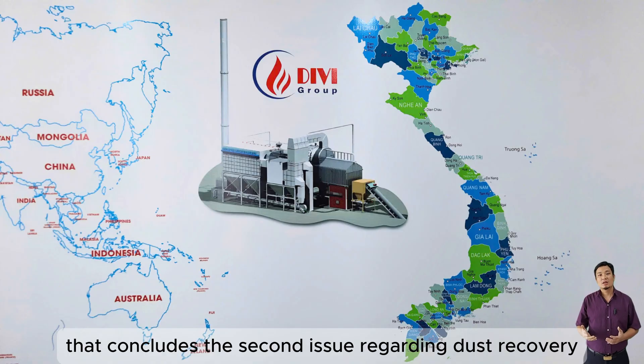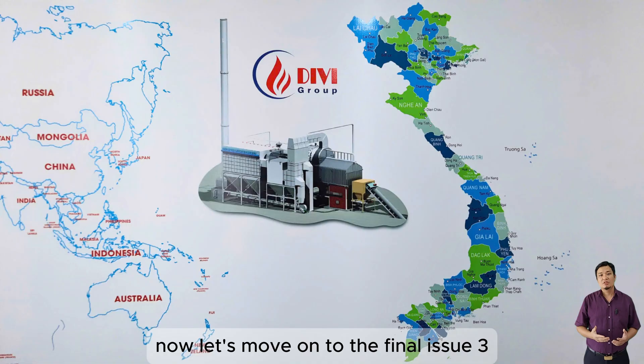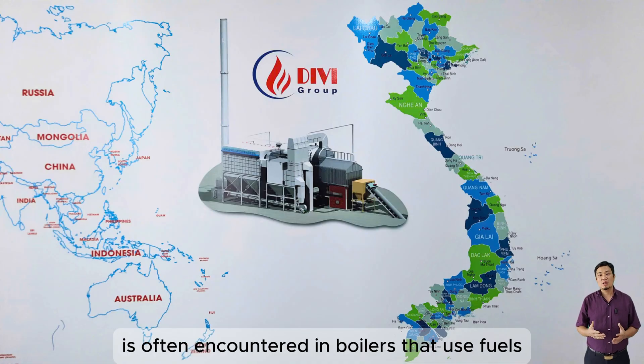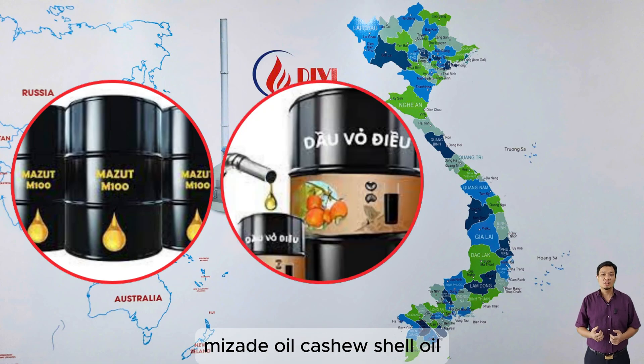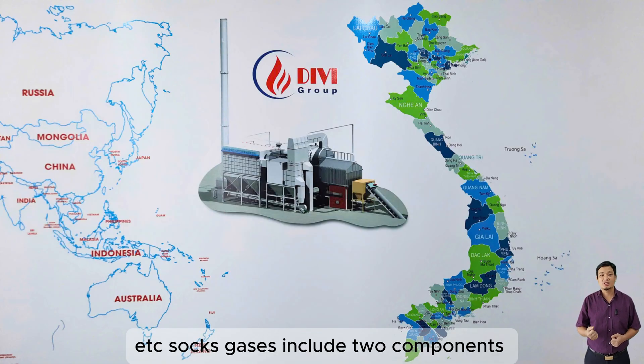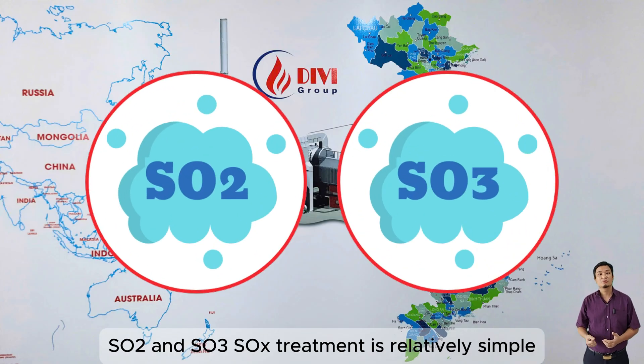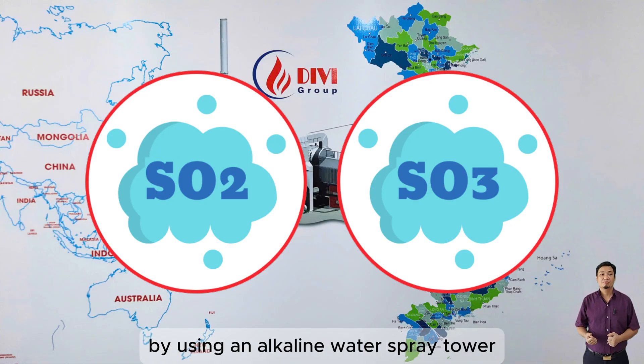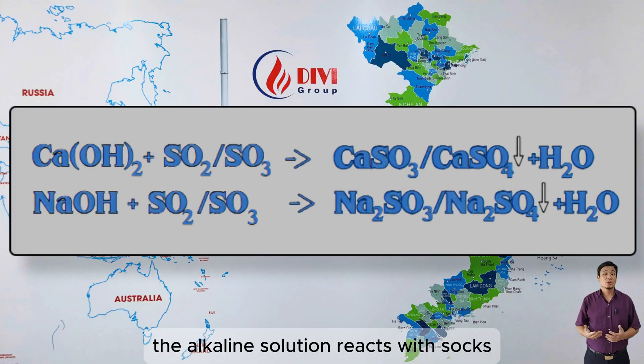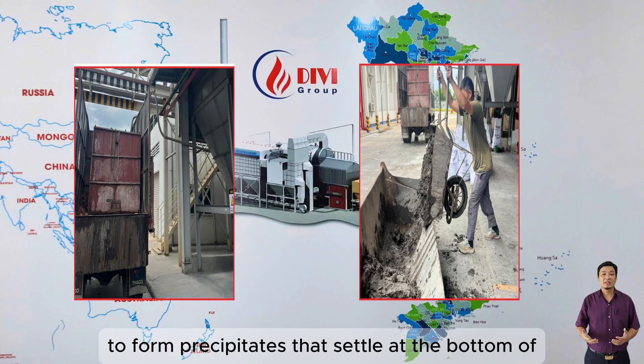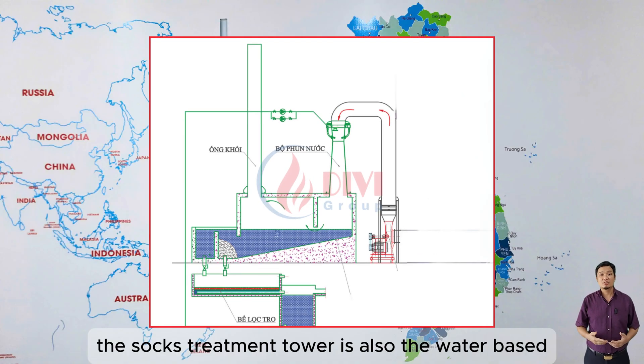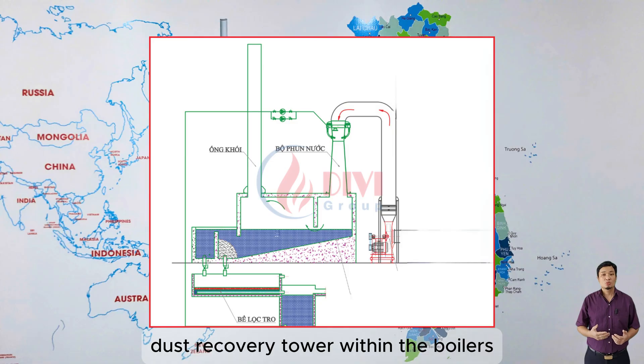That concludes the second issue regarding dust recovery. Now, let's move on to the final issue. Issue 3: SOx gas treatment. SOx gases are often encountered in boilers that use fuels high in sulfur, such as FO mazut oil, cashew shell oil, recycled rubber oil, coal, etc. SOx gases include two components: SO2 and SO3. SOx treatment is relatively simple by using an alkaline water spray tower, commonly lime water Ca(OH)2 or NaOH. The alkaline solution reacts with SOx to form precipitates that settle at the bottom of sedimentation tanks or spray towers for further collection and treatment. Typically, the SOx treatment tower is also the water-based dust recovery tower within the boiler's dust recovery system.